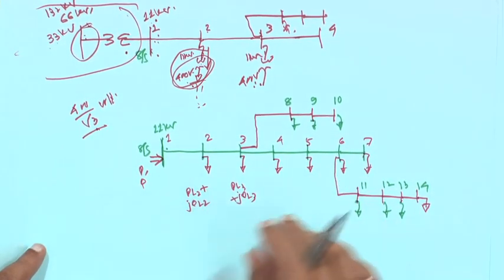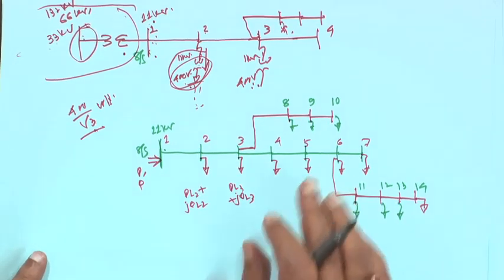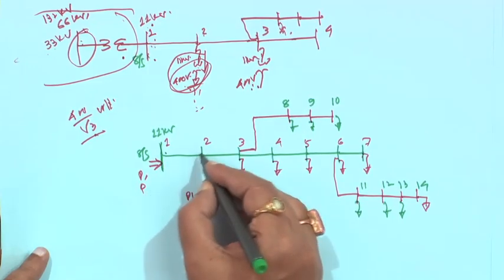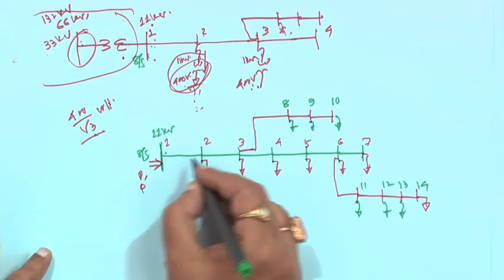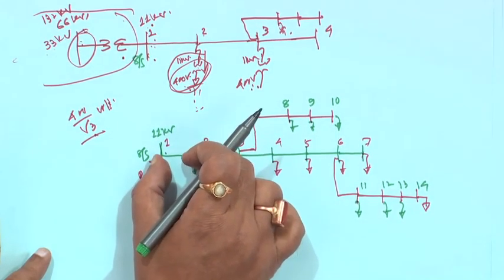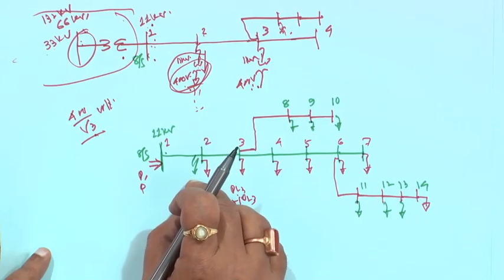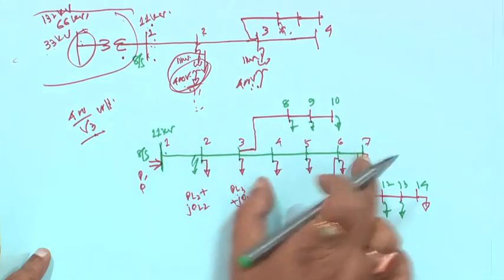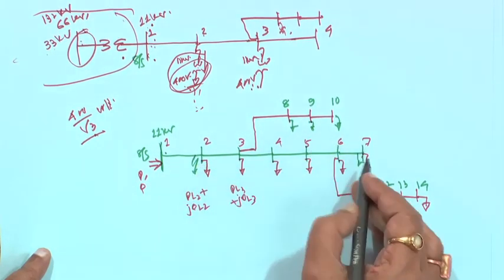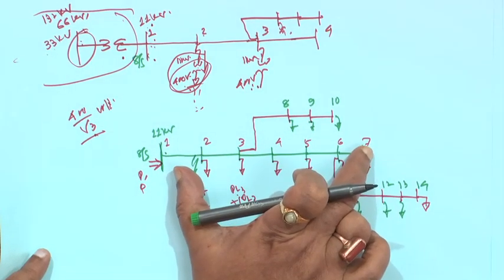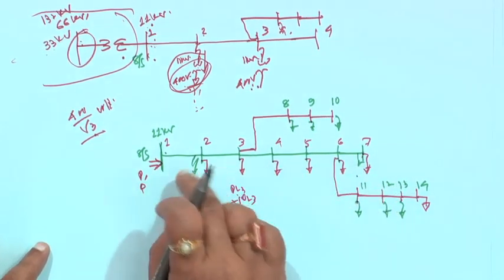Now, the question is why it is radial. For better protective coordination. Suppose a fault occurs very close to the substation, somewhere here. It will encounter very small impedance, so the fault current will be high. But if the fault is somewhere far away, then the total impedance from here to here will be higher. If a fault has occurred, everything will go to the fault. So the impedance will be very high, and that is why the fault current will be lower.